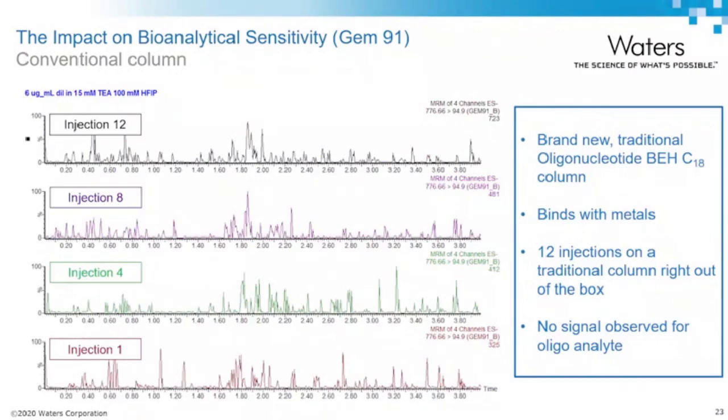This is reflected here on the example. The data come from Mike Donegan, my colleague, one of those days when he developed the method and prepared LCMS calibration, in an attempt to go to a wider and longer study. He switched to a new column, and the signal from injection number 1, 4, 8 to 12 was lost. And it was not obvious why it is lost.